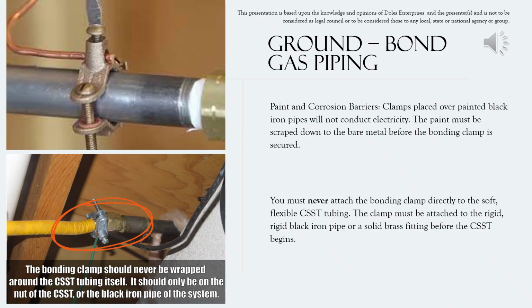Now, to touch on a couple of things, I do want to point out that as far as the bond goes, you should have them sand or remove the coating or any paint or anything like that before you put the clamp on. The paint must be scraped down to bare metal so you can make sure you get a good bond. That's one point. Now, getting back to the CSST, one of the things you look for too is that grounding clamp. It doesn't need to be on that thin metal tubing. It should be on the fittings, the hard fittings above it, brass or black iron, whichever one it may be.